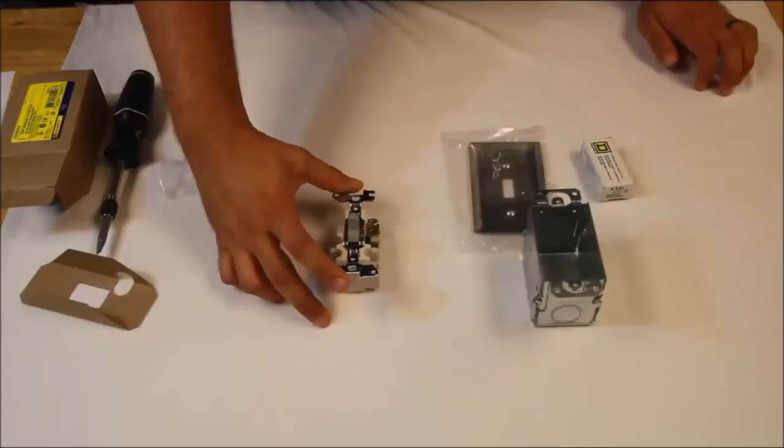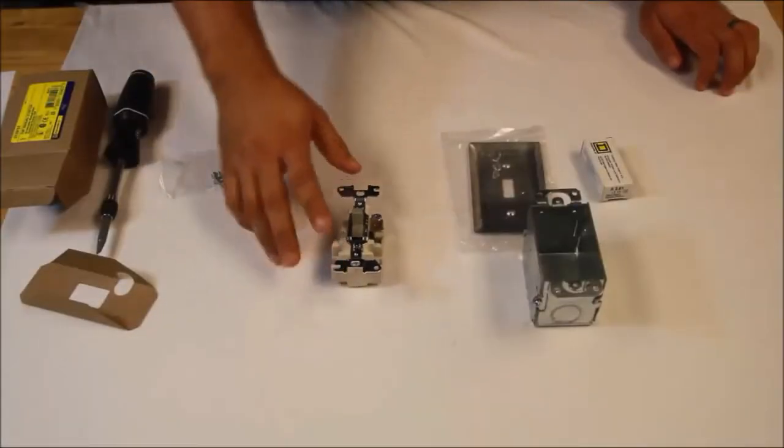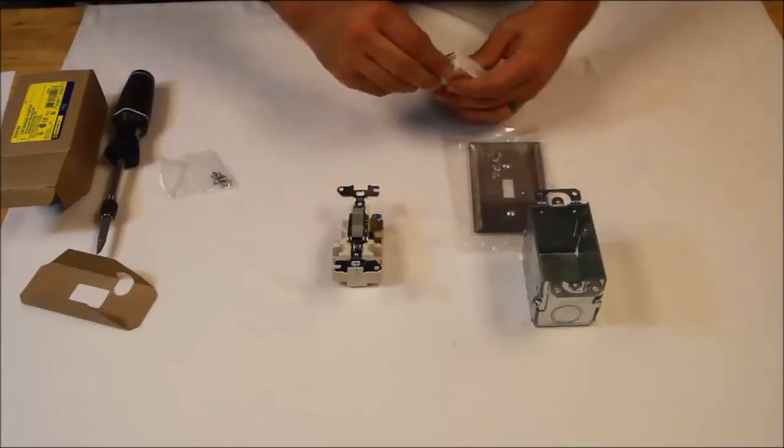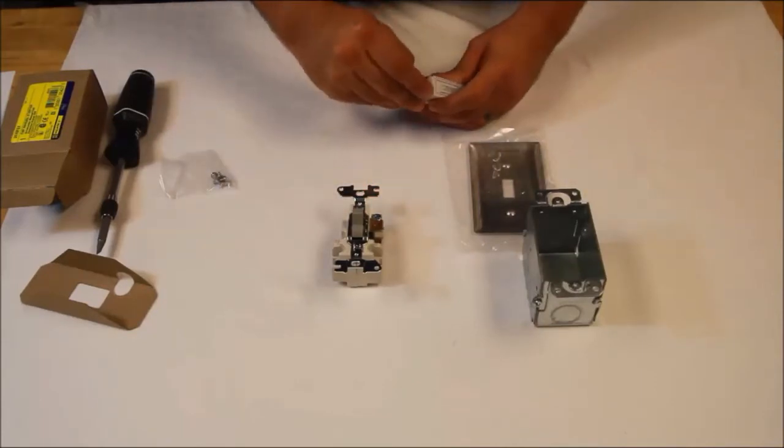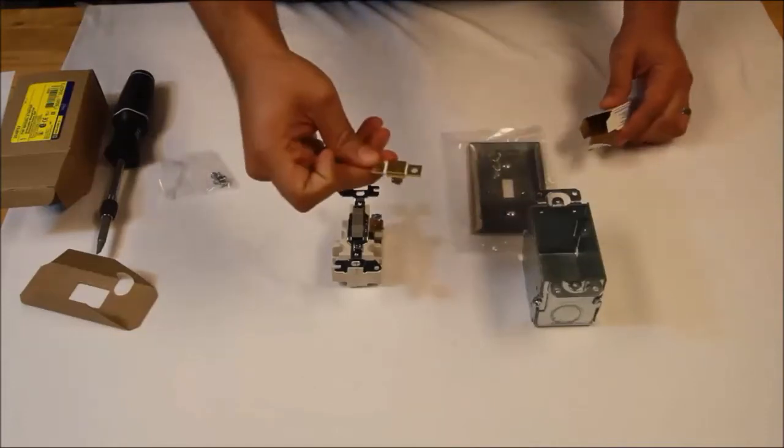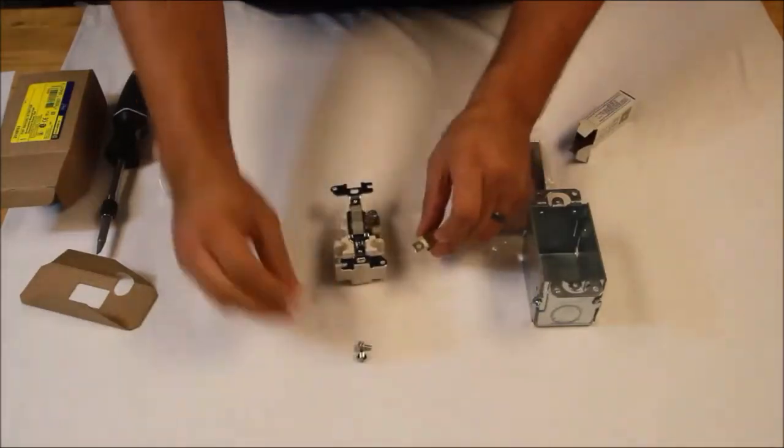The fractional horsepower manual motor starters from Square D come without thermal units. Thermal units are sized based on our thermal unit selection table for full load amperage. These devices will come pre-packaged with one thermal unit as well as two mounting screws.